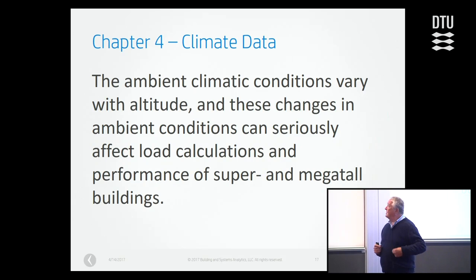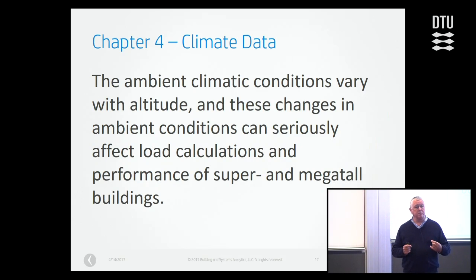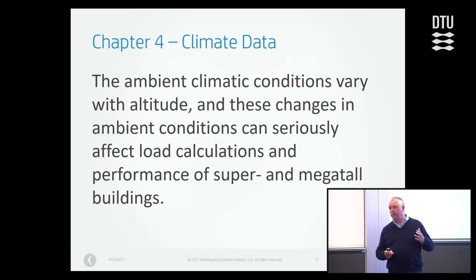The ambient climate conditions change with altitude. A typical rule of thumb is the temperature degradation will be 6 degrees Celsius per 1,000 vertical meters. So don't forget, we're talking at 600 meters plus.